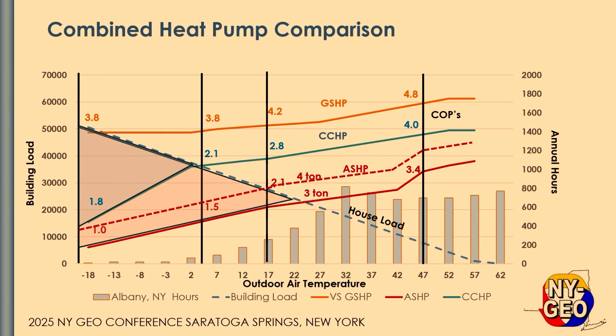for the cold climate heat pump, you would have to add in whatever you're putting in for your auxiliary, which would be most likely electric, but it could be natural gas depending on how you've got your system configured. So that really is the result there of high COPs can be good, but you've also got to look at the capacity of the equipment for that COP.